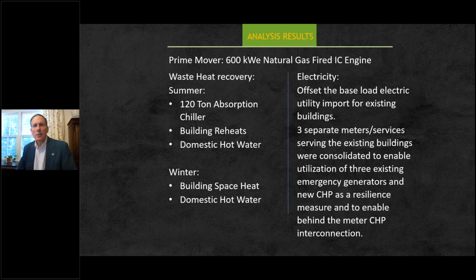The result of the analysis was that the facility would be able to utilize a 600 kW natural gas-fired internal combustion engine. On the thermal side, from waste heat recovery in the summertime, the system would drive a 120-ton absorption chiller, also supply heat to the building reheats, and provide heat for the domestic hot water systems. In the wintertime, the system would provide building space heat and also the domestic hot water system.